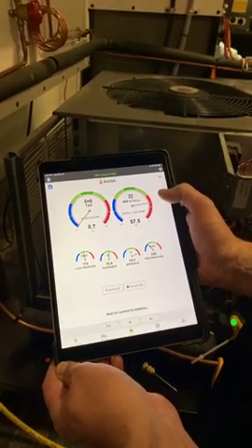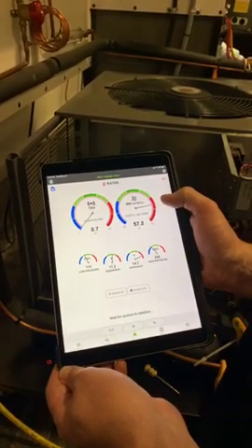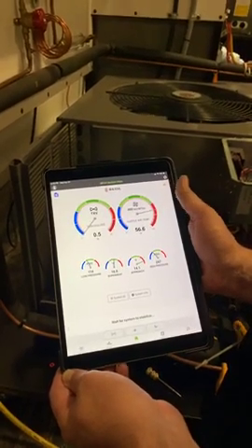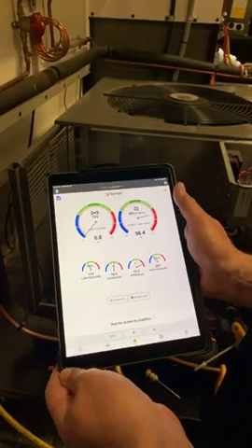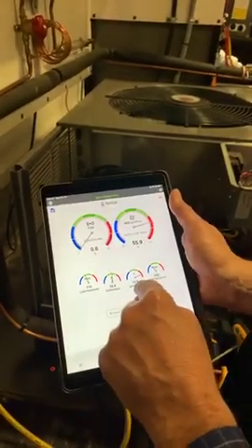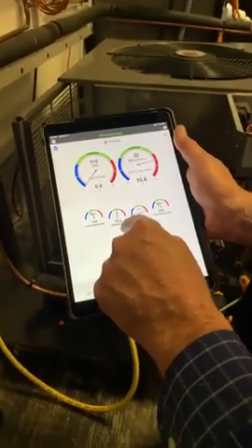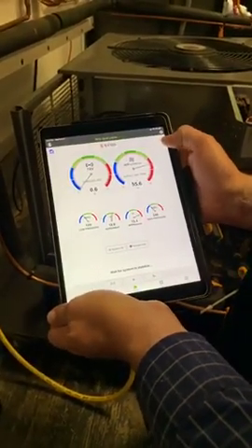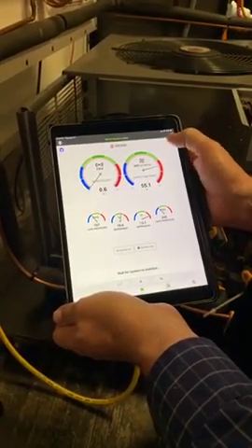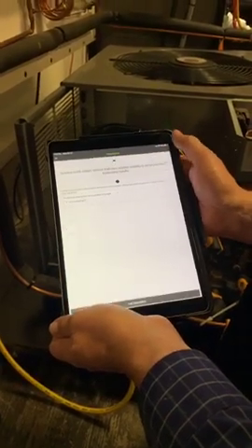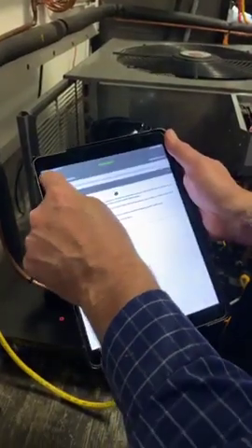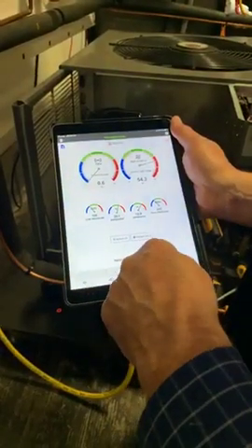So what we're looking at is return air and the split. But we're looking at just the supply air temperature because it's a little bit smoother of a metric. We're watching our subcooling and our superheat to make sure those are stable, and watching our liquid line and suction line temperature. So this is our stability algorithm that's running up on the top there. We tap on that, it'll tell us right now our temp split's not stable, and that's our primary driver for that right at this second.